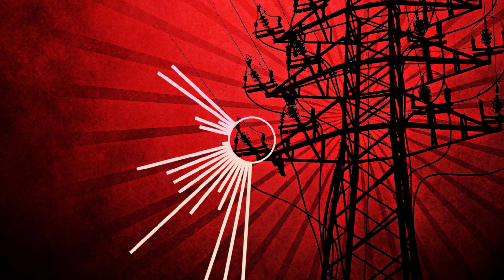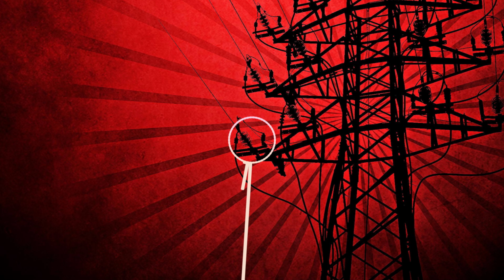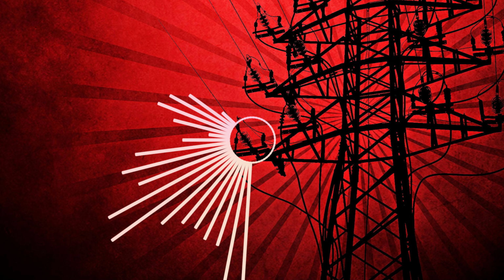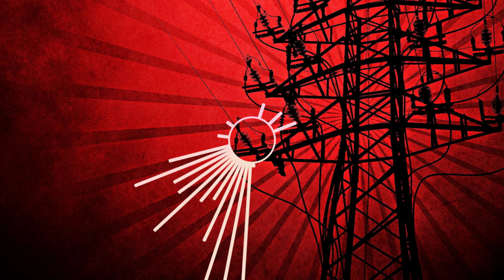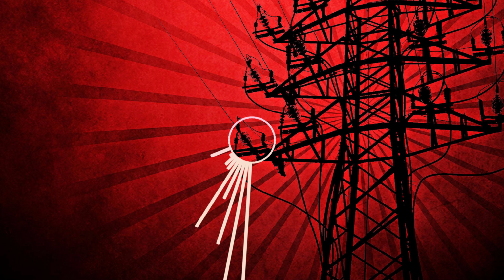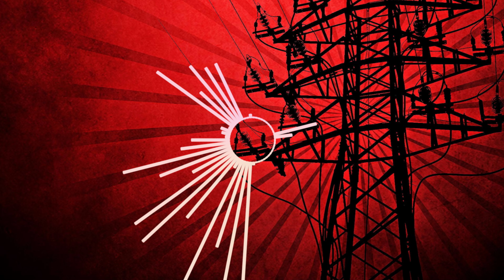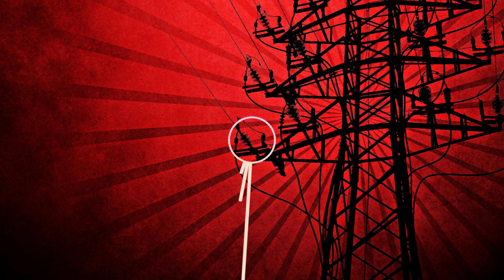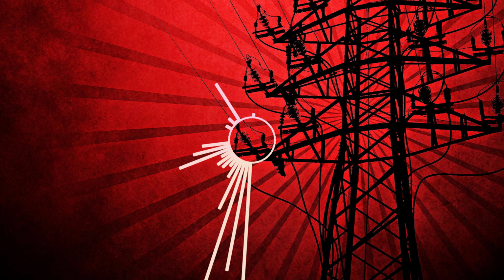Let's make this real with an example. Imagine you hire an electrician to install a new circuit breaker panel in your home. If the electrician ignores 110.12, here's what could happen: unused holes might be left in the panel, wires might get tangled or disorganized, and moisture, dust, or pests could get into the electrical panel, causing corrosion or electrical failures.